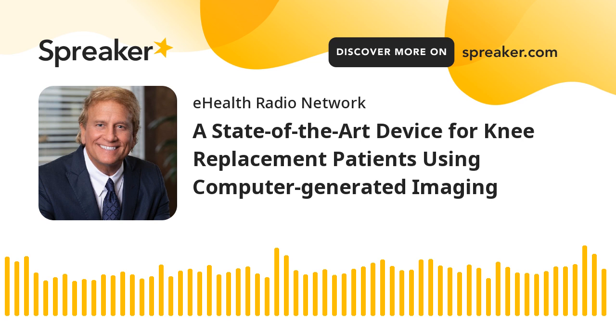Traditional methods require the surgeon to assess the balance by examining the knee at the time of surgery, basically using his experience and a feel of how tight or how loose the ligaments are on one side of the knee versus the other. The BalanceBot is a technique where a defined load is applied, and this is done prior to performing the procedure, where I can assess the pre-surgical ligament imbalance and then very accurately position the implant literally within a half a millimeter and a half a degree of rotation in order to balance the knee.